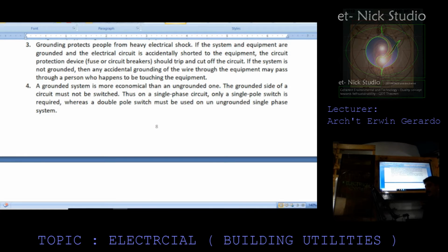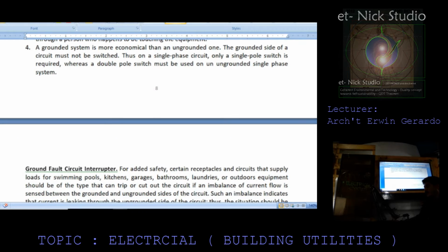Three, grounding protects people from heavy electrical shock. If the system and equipment are grounded and the electrical circuit is accidentally shorted to the equipment, the circuit protection device, fuse, or circuit breaker should trip and cut off the circuit. If the system is not grounded, then any accidental grounding of the wire through the equipment may pass through a person who happened to be touching the equipment.